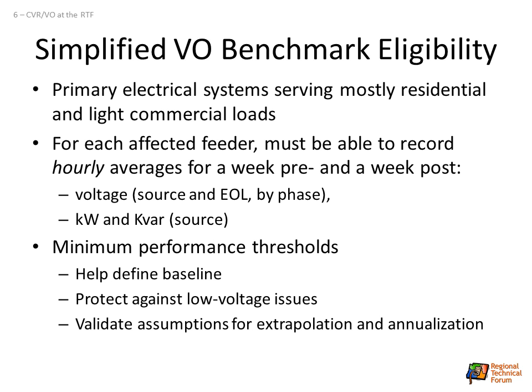The performance thresholds also help protect against low voltage issues. Tom mentioned that earlier—you need to know what's going on all along your feeder, because when you lower voltage at the source, somebody close to end of line might be experiencing problems. So your measure wouldn't last very long. Probably then they would complain.